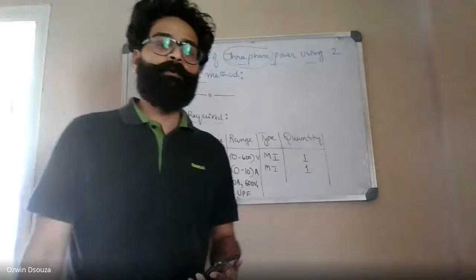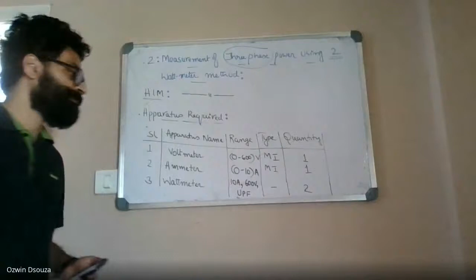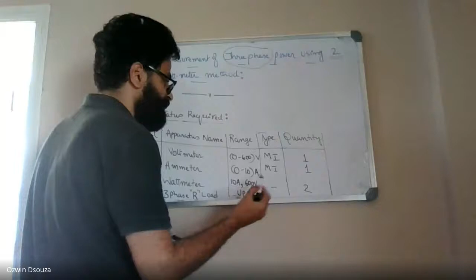So that's the range: 10 ampere is taken from the ammeter range, 600 volt is taken from the voltmeter range, and UPF because you are using a resistive load, which is a unity power factor load. For type, you can just put a hyphen, and quantity 2, because you're using the 2 wattmeter method. You can also write a fourth item: 3-phase load, 3-phase R load, R load being resistive load, with no range and no type, and quantity 1.